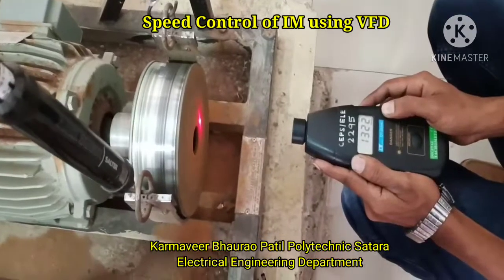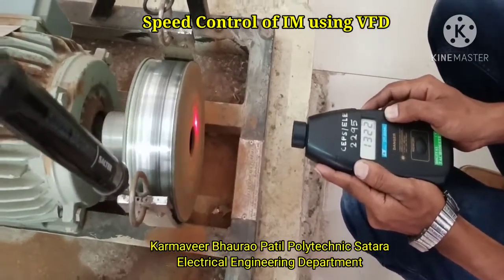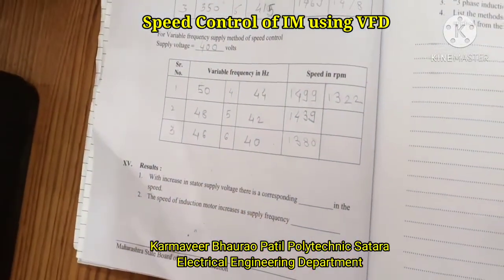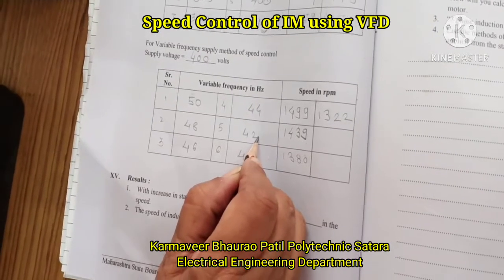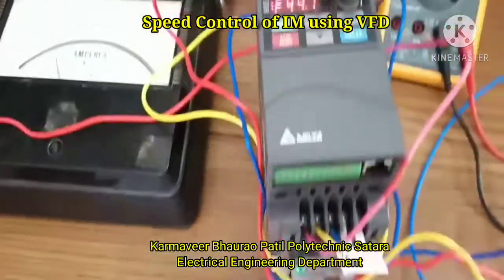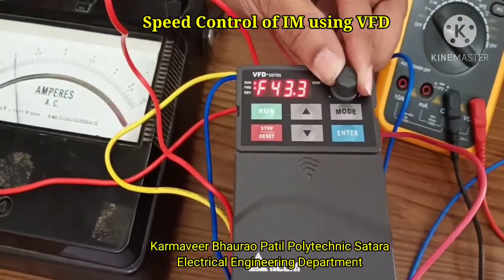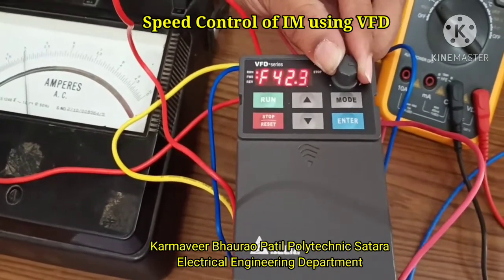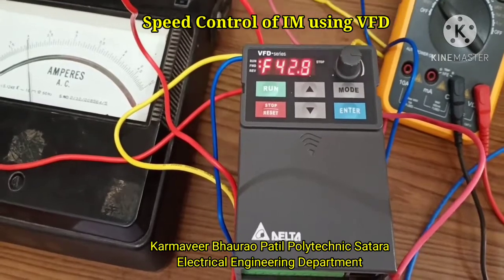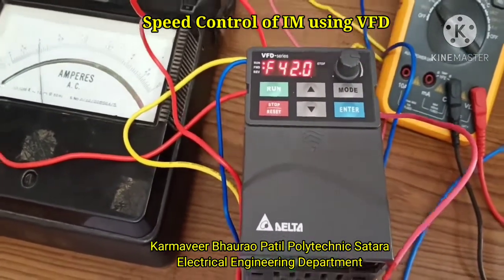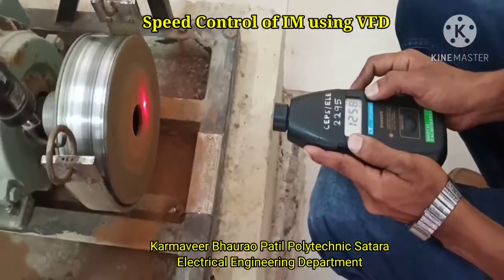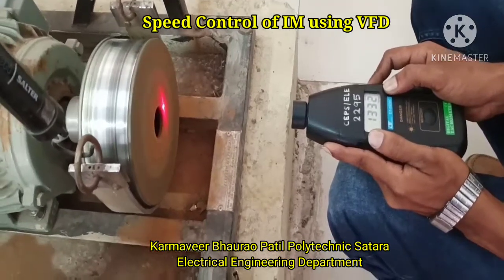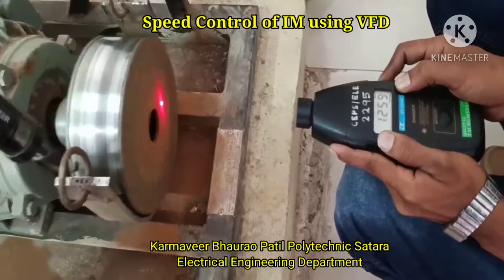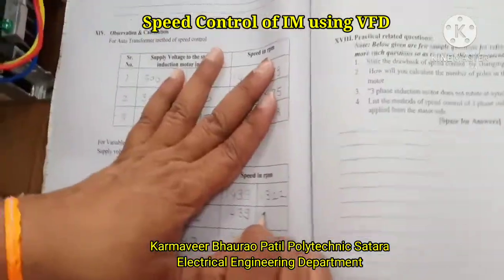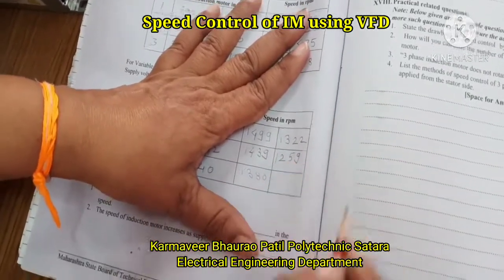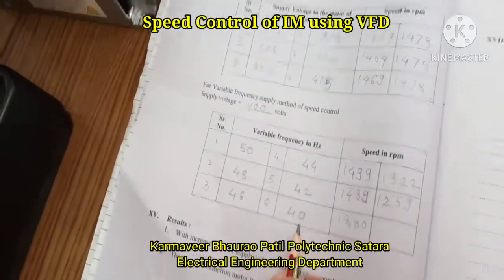Speed is 1322 rpm. Now let us adjust the frequency to 42 Hertz. It is very sensitive. We have to adjust it smoothly. It is 42 Hertz. So the speed is 1259 rpm. And now our last reading is for 40 Hertz.